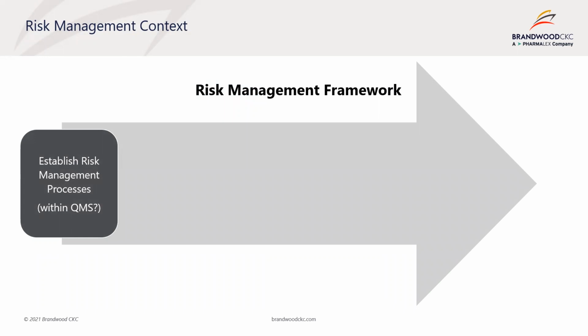The first and foremost in the framework is the establishment of the risk management processes. These are the internal procedures and workflows that marry the risk management requirements to the business processes. They identify the internal requirements: when, who, and how the activity must be conducted through the various processes. Because not all countries require a quality management system for medical device manufacturers, a certified quality management system is not required for showing compliance to the regulations. However, a quality management system is extremely helpful in managing risks properly. Because of this, and because most medical device manufacturers do employ a quality management system, the framework that we'll discuss in this webinar is constructed so that it will be easily incorporated in the quality management system that a manufacturer has or will establish.